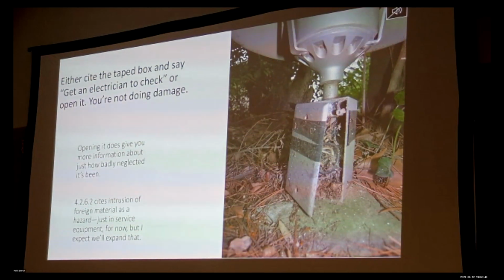One of the things that's not in that point, but later on we say, under the section for service equipment - I think we're going to move it up in our August meeting - is if foreign materials have gotten in. That's big. This is not just a matter of replacing those screws, maybe the gasket, and replacing the cover and you're good. That's bad news. It's very lucky if there isn't further deterioration there.